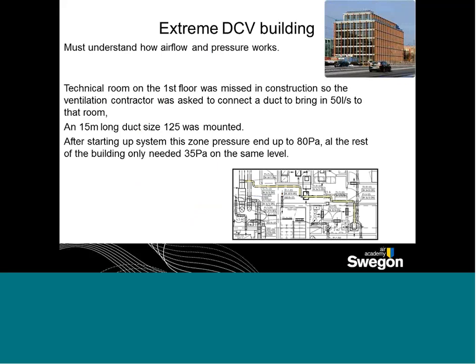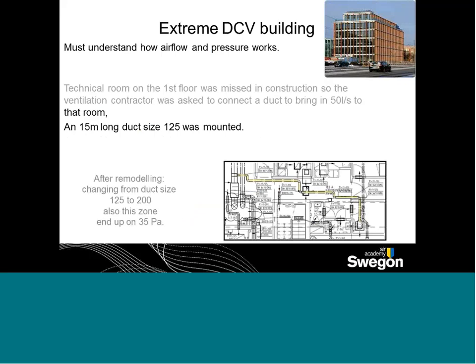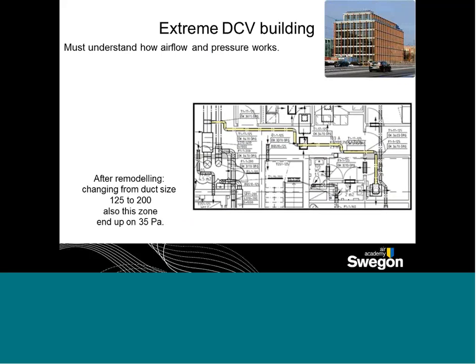One thing I wanted to highlight: during construction they actually missed one of the technical rooms and put in a 15-metre-long duct to supply some CAV volume into that space. It took the whole system out of balance. They didn't really consider the impact of putting in the CAV system on the rest of the system. So they had to remodel it — changing from 125 millimetres up to 200 millimetres — which lowered the pressure drop, and everything was then in perfect balance at 35 Pascal again. It just needs to be considered and thought through how airflow and pressure work together.